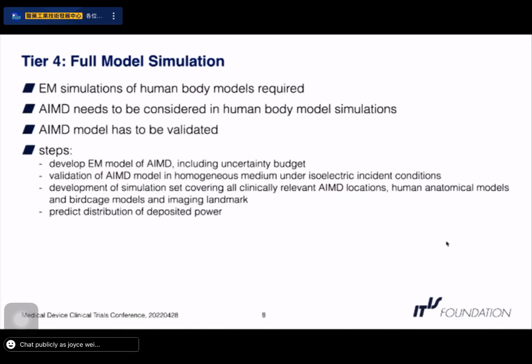Tier 4 is the most complex part of the ISO 10974 that can be used to determine the deposited power of an active implantable medical device. And this is basically also a tool that we use as a validation for the IM analytics, where we look at the worst case or some of the worst cases of an implant, a VIP model, a bird cage model, and a scan position. And we actually take the EM model of the implant, we place it in the VIP in our numerical model, and then we run the full simulation and we extract the power deposition, also the temperature rise, and it should be the same as what IM analytics is giving.